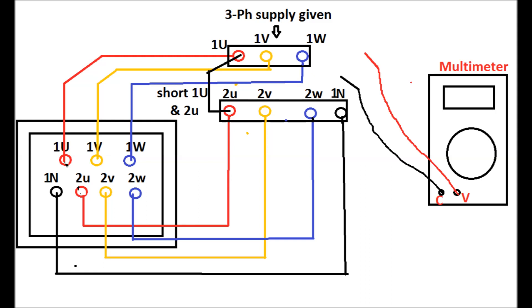Color-coded wire is connected to the primary winding and from the secondary winding and neutral, similar to the YNd1 arrangement. Three-phase supply has been given to 1U, 1V, and 1W, terminal 1U and 2U has been shorted, and by means of the multimeter different voltages have been measured.